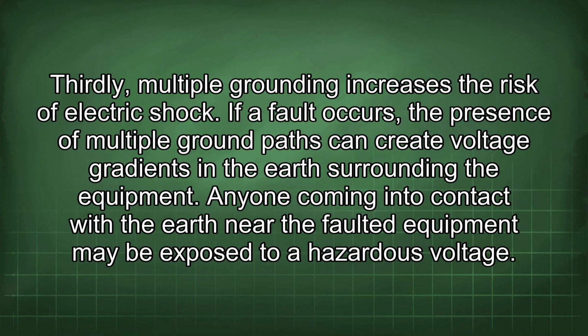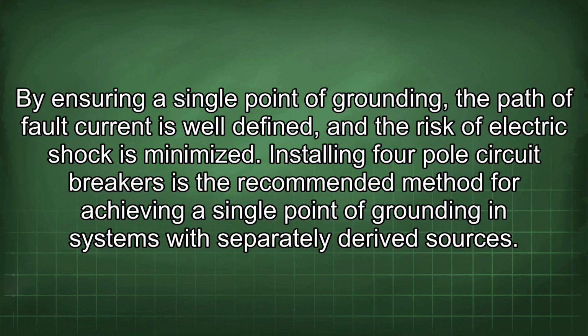Thirdly, multiple grounding increases the risk of electric shock. If a fault occurs, the presence of multiple ground paths can create voltage gradients in the earth surrounding the equipment. Anyone coming into contact with the earth near the faulted equipment may be exposed to a hazardous voltage. By ensuring a single point of grounding, the path of fault current is well defined and the risk of electric shock is minimized. Installing 4-pole circuit breakers is the recommended method for achieving a single point of grounding in systems with separately derived sources.